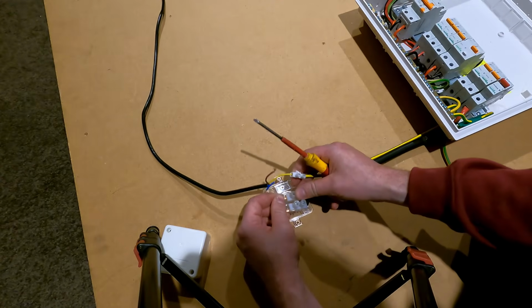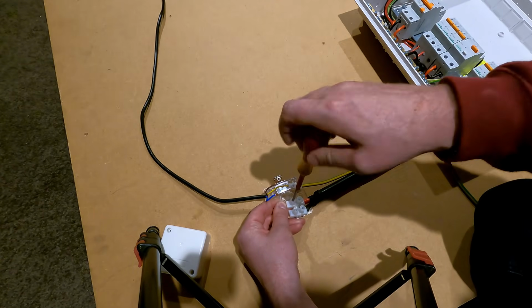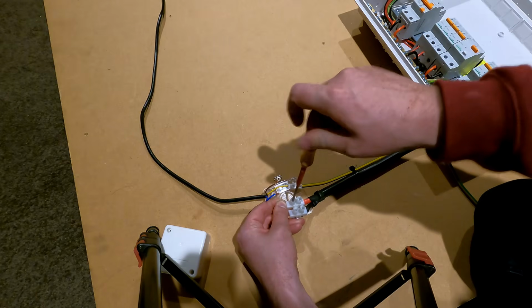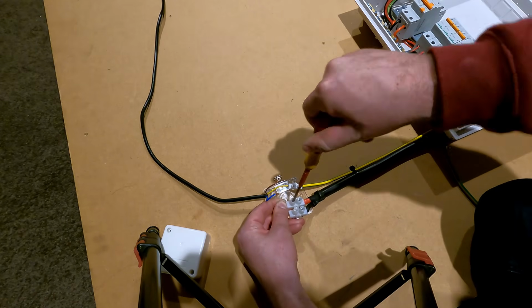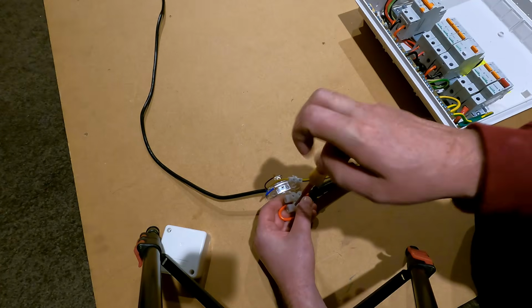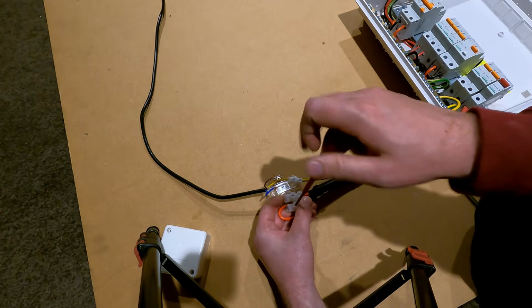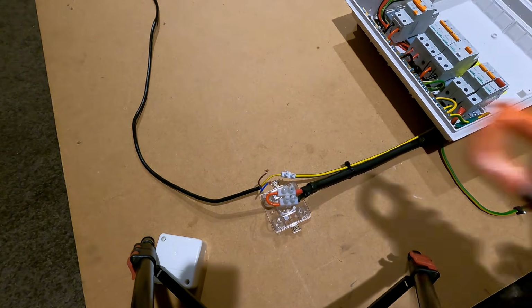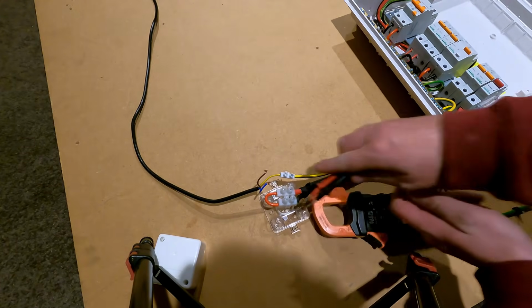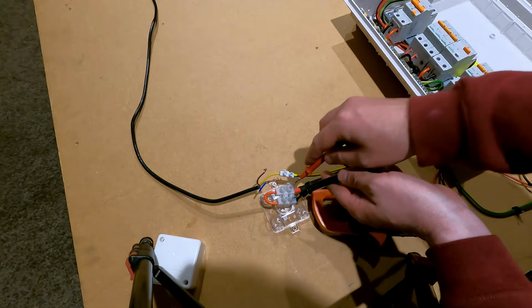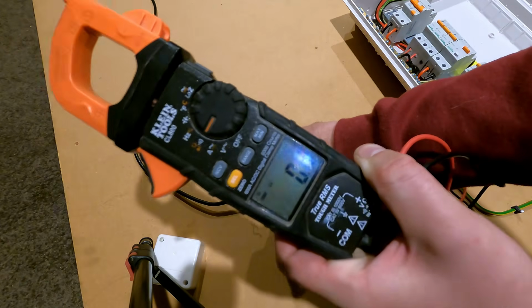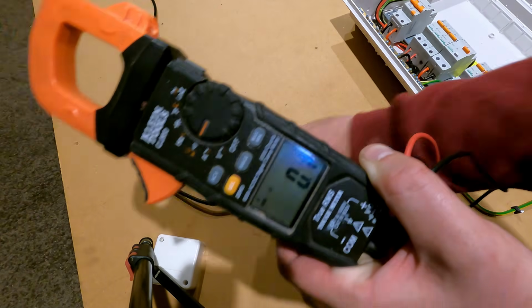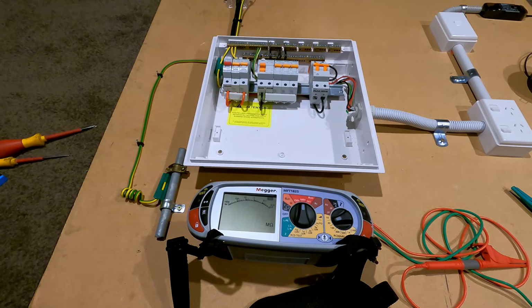Now these three tests so far are all tests that have been done without electricity turned on. You don't want to be doing these when the installation's live. You want to have verified that everything's okay to liven first. What I'm going to do first is just test to ensure that these two terminals are definitely shorted out, and as you can see we've got 0.01 ohm. We've got this installation to do a test on.